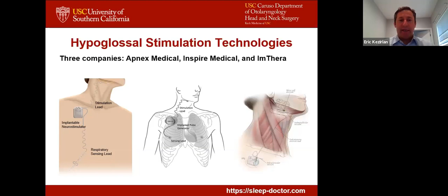So obviously, we want to treat sleep apnea, and you have this system that delivers hypoglossal nerve stimulation. I'll talk more about it. But the big question that comes up is, do we improve airflow? And then does it wake patients up? Again, there are many things here from data collected on a PSG, but we'll focus on airflow towards the bottom. Inspiratory airflow is a downward signal, and expiratory airflow is upwards. Here the inspiratory signal is pretty flattened, associated with airway obstruction. At the bottom is a certain level of stimulation, 1.7 milliamps, which is the way this system was set, based on the intensity of the stimulation. If you're not getting the airway open and good inspiratory airflow, you turn it up.